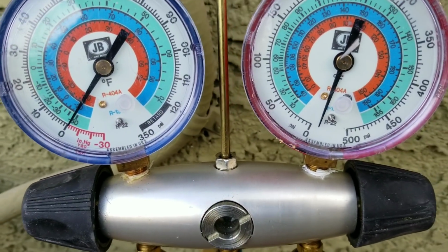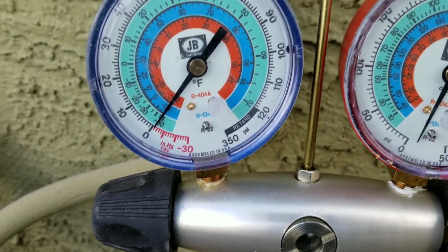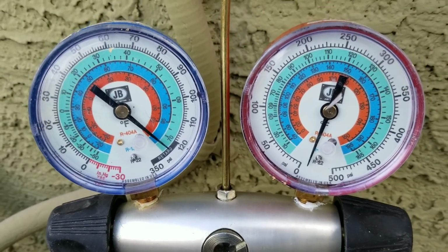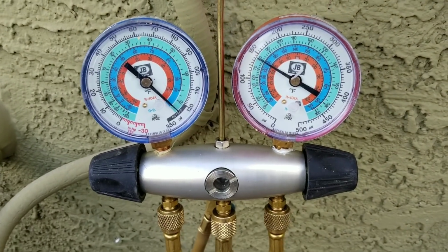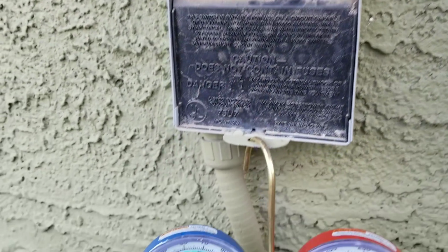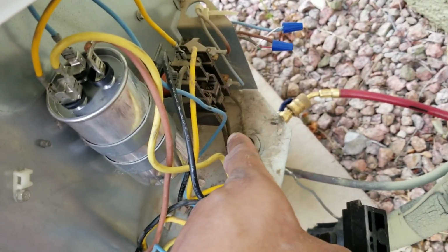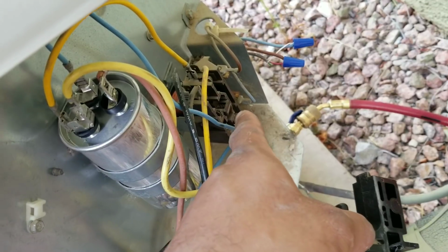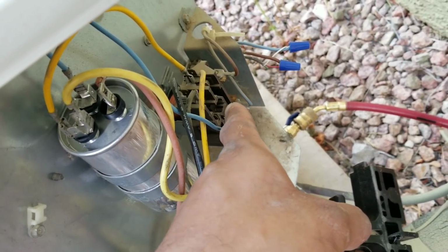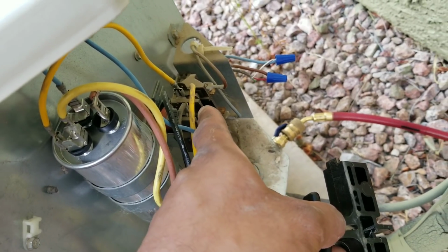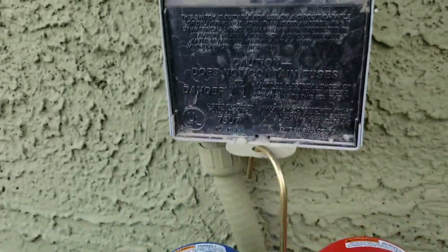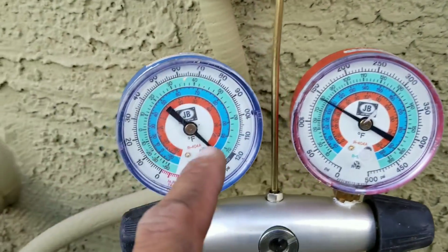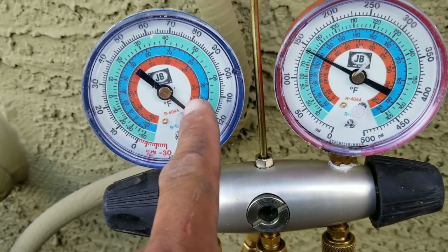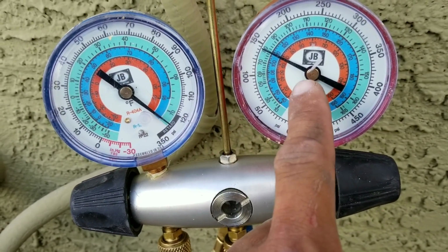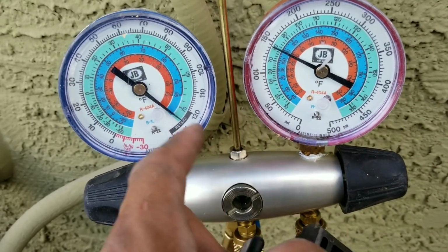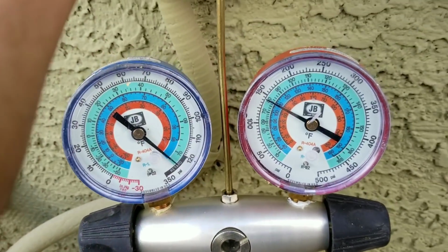Right now I'm putting in my low side, and you'll see my needle will move on my gauges. That's my low side, my high side. Plug in my disconnect. That will send 240 volts to my contactor. The contactor is already engaged, calling for 24 volts from the thermostat. That will send 240 volts up to the contactor to my compressor. And as soon as I put this disconnect in, the system should start up right away. You'll know because once I plug in my disconnect, the readings on my gauges will start to equalize, and you'll get the reading of the system.